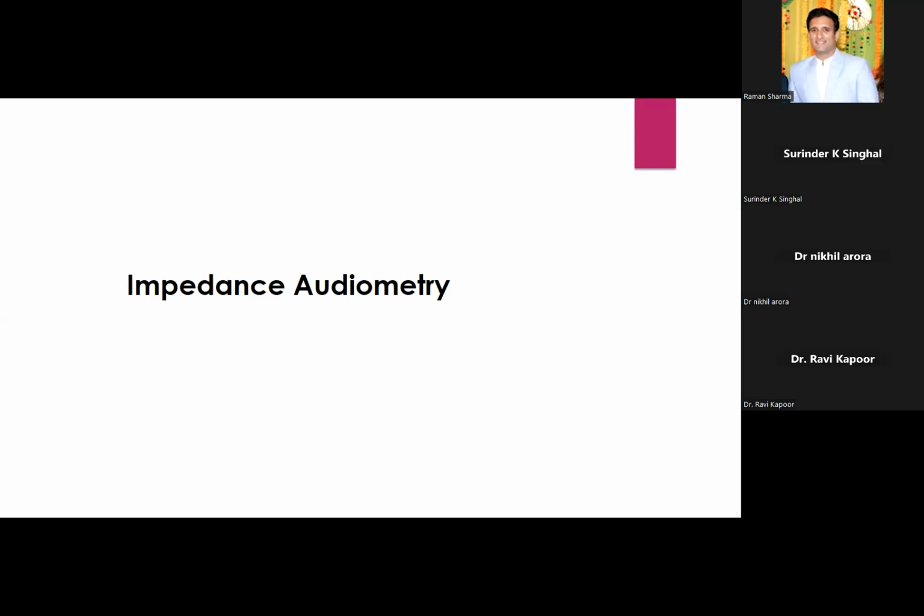Since narrow band noise is frequency specific, we prefer narrow band noise as compared to white noise. But in cases where the audiometer itself does not incorporate the facility of narrow band noise, then we at least have white noise, or wideband noise, for the sake of masking. So definitely narrow band noise is preferable. I hope this answers the query.